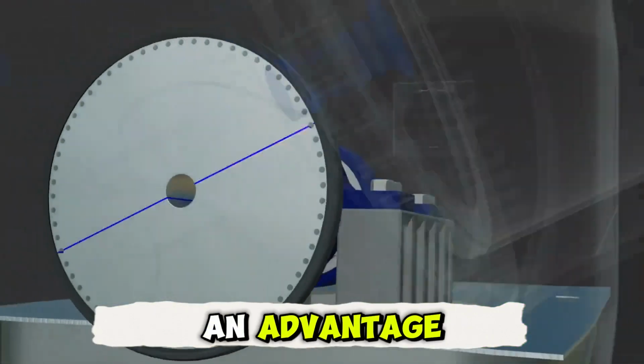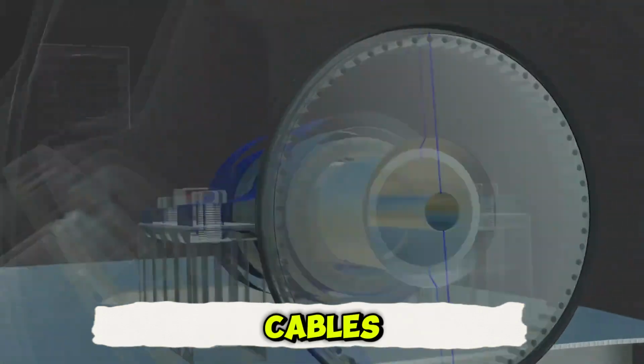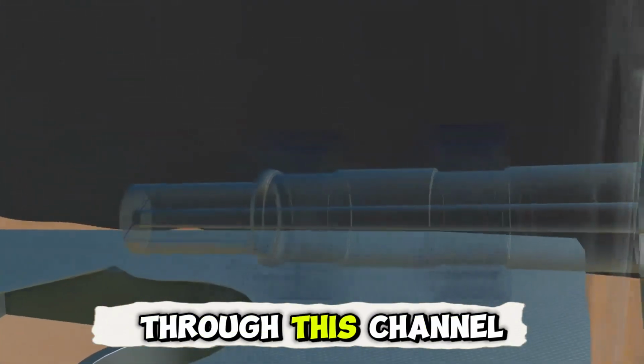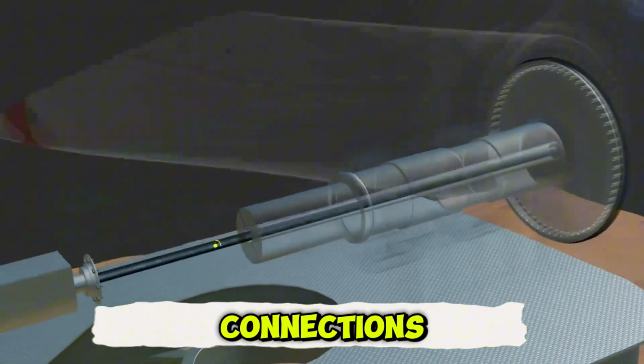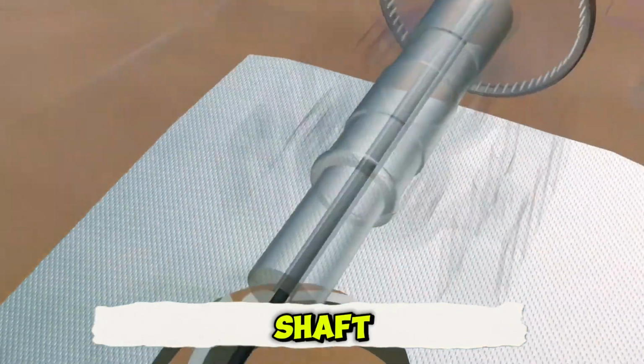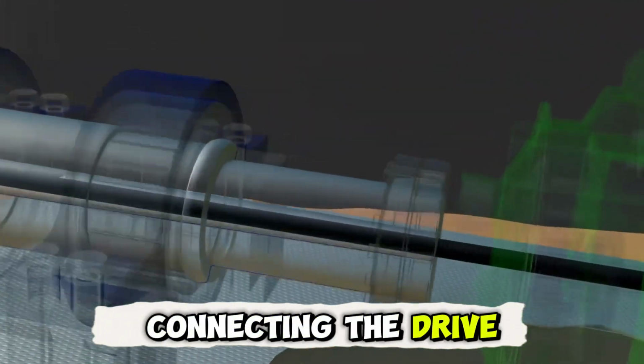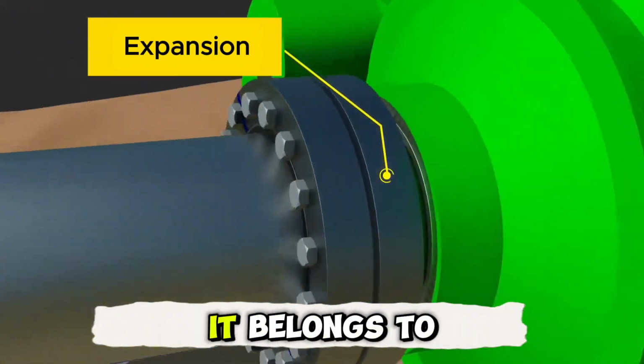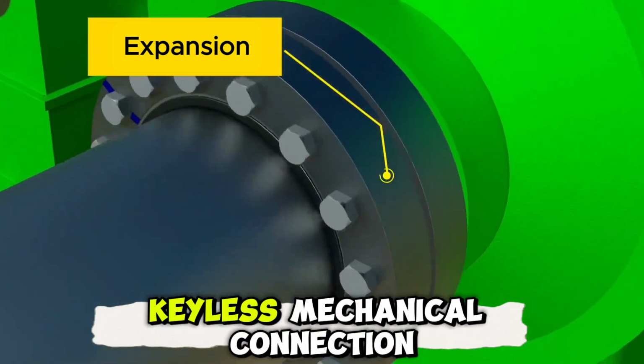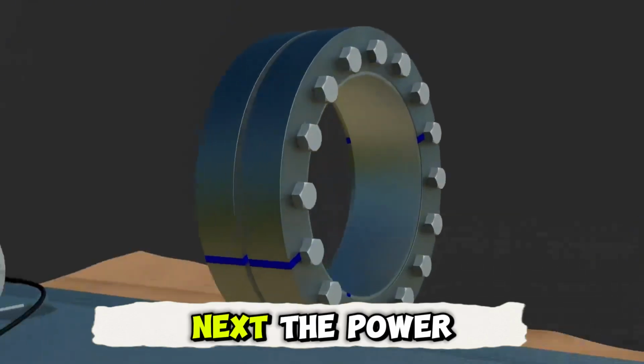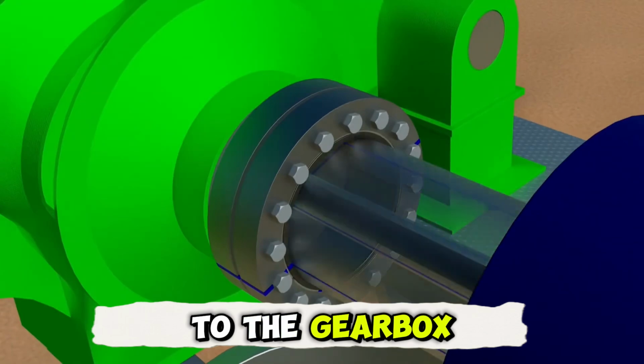This design has an advantage. The wires or cables used by the equipment can pass through this channel to make electrical connections. At the end of the drive shaft, a shrink disc is also connected, tightened with a sleeve connecting the drive shaft with the gearbox behind it. It belongs to a high-strength keyless mechanical connection. Next, the power will be transmitted to the gearbox at the back.